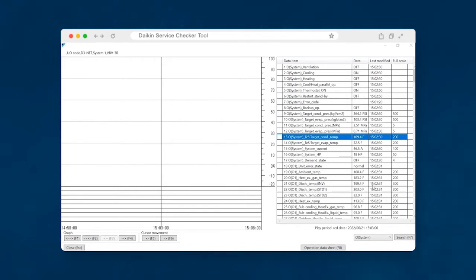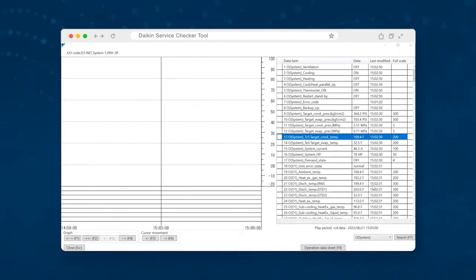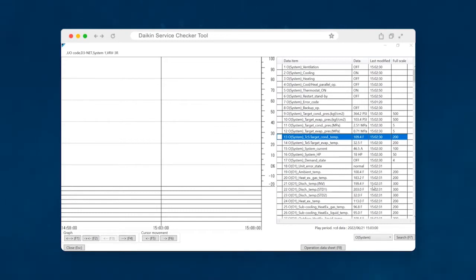The Daikin service checker is a piece of hardware that is used in accordance with a piece of software that allows us to get an inside look at the operational data of the system. We can see outdoor unit data points such as temperatures, pressures, indoor temperatures, and things such as that. And so with this data, we're able to make diagnostics and confirmations. System health checks, it's a very valuable tool if you're going to be working on the VRV system.